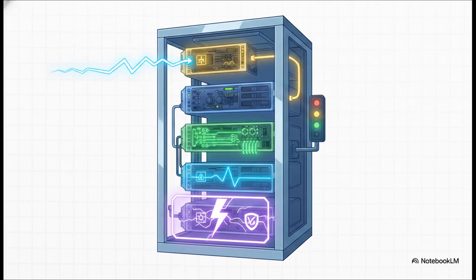First up, the SMPS panel takes your standard 230-volt AC input and converts it into a stable 110-volt DC just to charge the battery bank. Next, the DC distribution panel, or DC-DP, takes that 110-volt DC and chops it way down to anywhere between 6 and 60 volts.